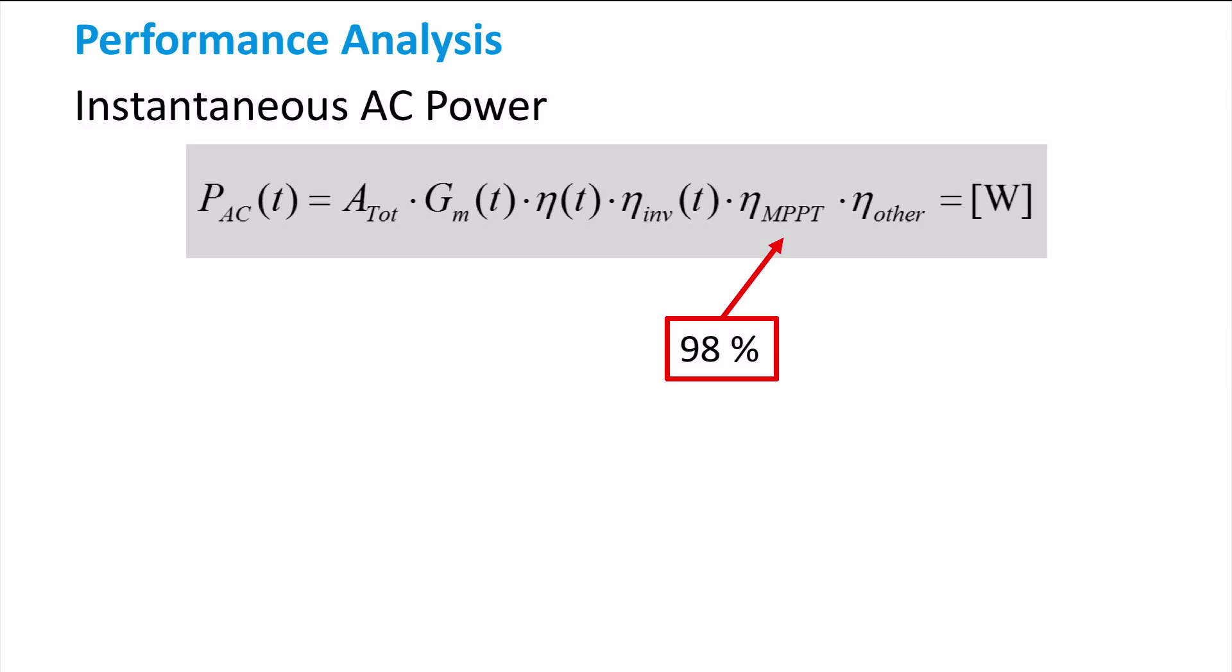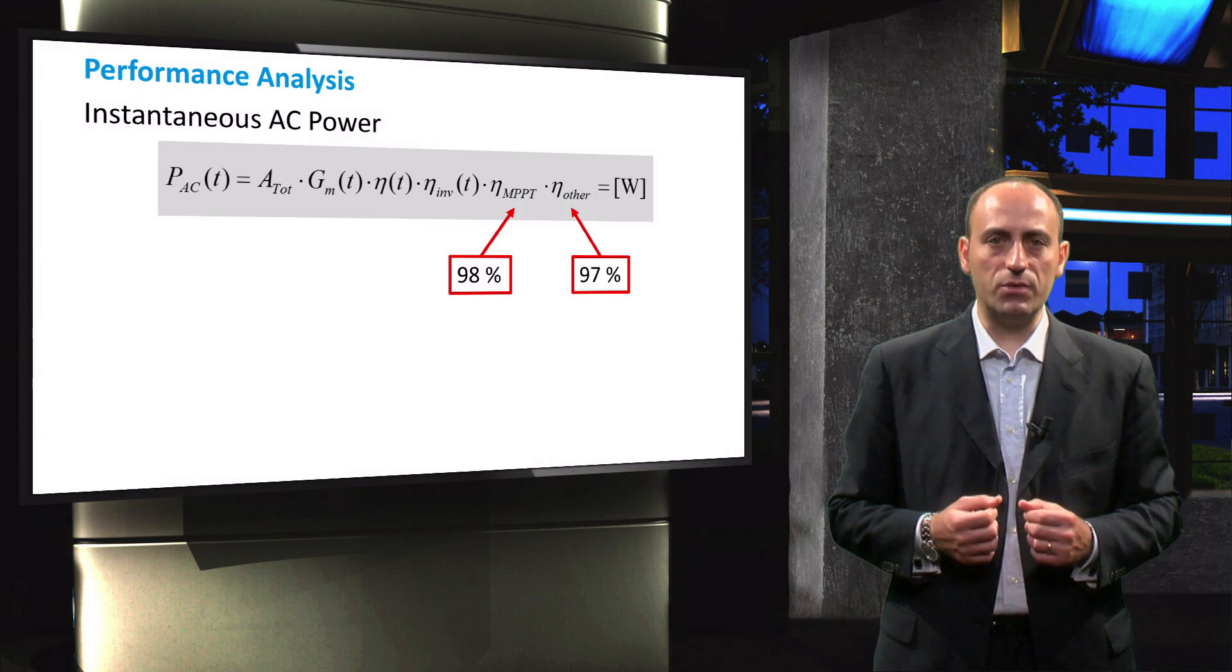For a more advanced analysis, you can also calculate its instantaneous values by coding and simulating the MPPT algorithm separately. In the other efficiency parameter, soiling, cabling and any other losses that could occur in a PV system are included. This efficiency parameter is usually set at 97%.